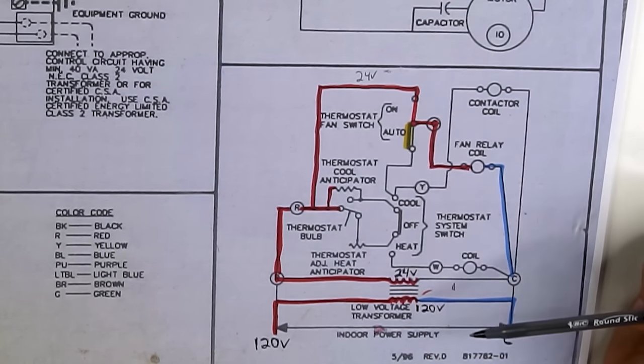All of these go to some kind of coil. Y goes to our contactor coil. W for heat goes through some limits then to a load like a gas valve coil. G goes to a fan relay. All go to common. And this is what a little thermostat would look like. We have a fan switch — in the auto position it's half colored in, the on position is on the other side. The thermostat mode switch is in the middle (off position), right is cool, and left is heat.